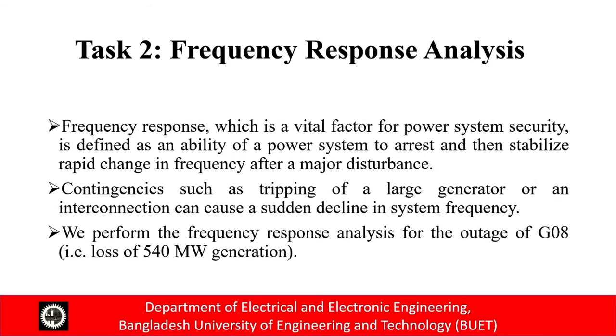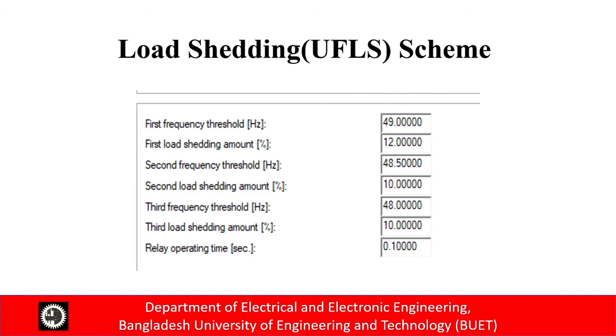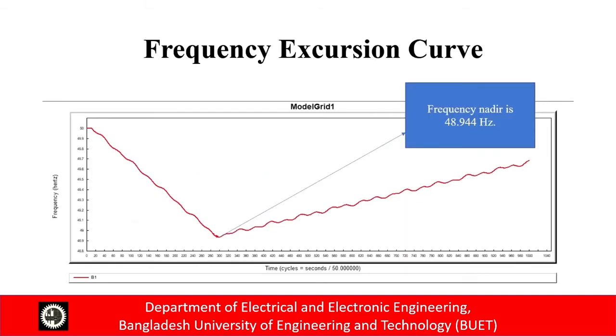Our Task 2 was to find the frequency response of the system. Frequency response is a vital factor for power system security, defined as the ability of a power system to arrest and then stabilize rapid changes in frequency after a major disturbance. Contingencies such as tripping of a large generator or an interconnection can cause a sudden decline in system frequency. We performed the frequency response analysis for the outage of generator 8. Here is the load shedding scheme and the frequency excursion curve. We can see the frequency nadir is 48.944 Hz.